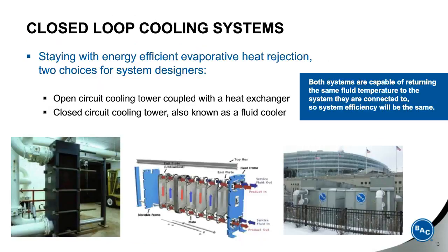So let's look at energy efficient evaporative heat rejection, which gives us two choices for system designers: an open circuit cooling tower coupled with a heat exchanger, or a closed circuit cooling tower, which is also known as a fluid cooler. You see a photo of a plate and frame there on the left. In the center, you see a diagram of the plate and frame pulled apart with the alternating hot and cold fluid paths through the plates of the heat exchanger. And on the right-hand side, you see a fluid cooler.